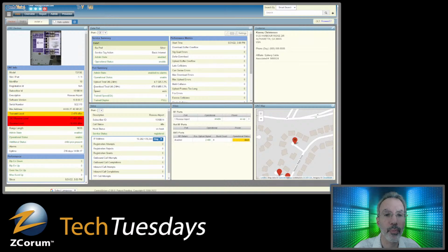And I can see here I've got a transmit level warning and a couple of alerts, the red color for OLT receive level and receive level. I've got a minus 17.4 dBm and a minus 16.026 dBm.